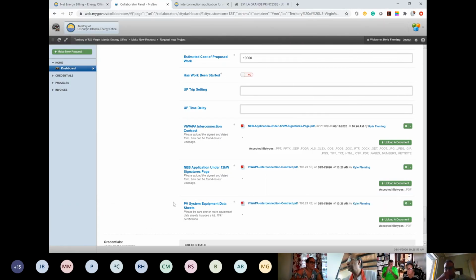So maybe you or somebody else in the meeting can answer: UF trip setting, does anyone know what that is, or UF time delay? I'll revert that to Ashley or anybody from the WAPA team who'd want to speak to the UF trip setting and UF time delay settings. UF is under frequency, so for instance if you experience an under frequency event, what's the time in which your system will trip or try to island itself if you have a battery?